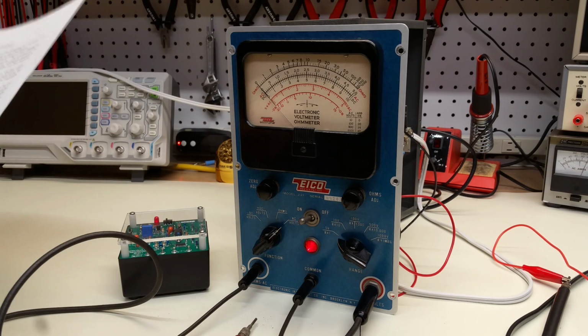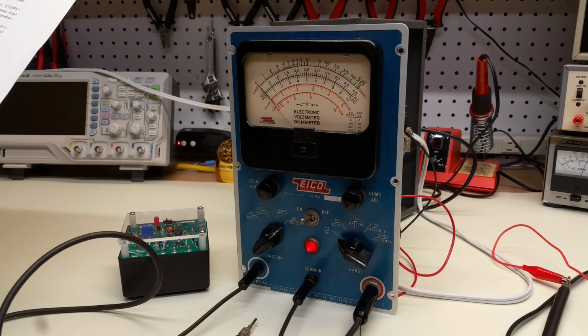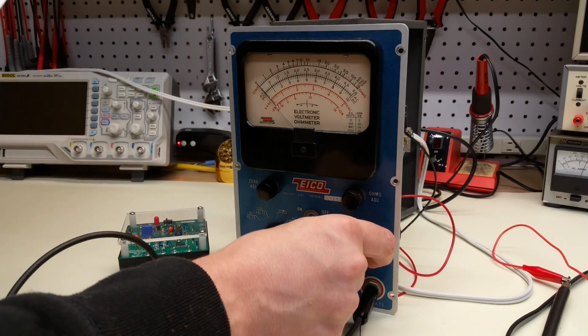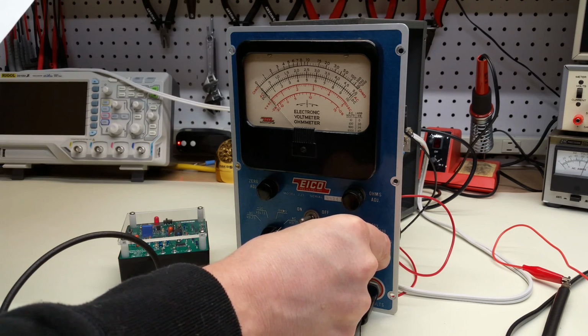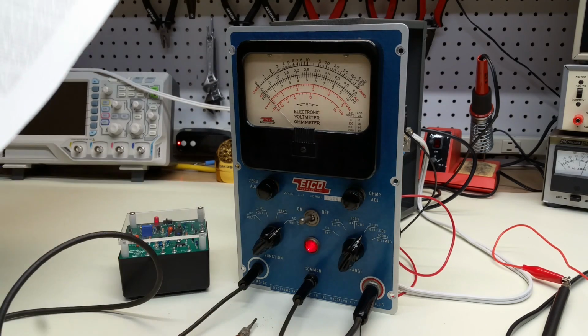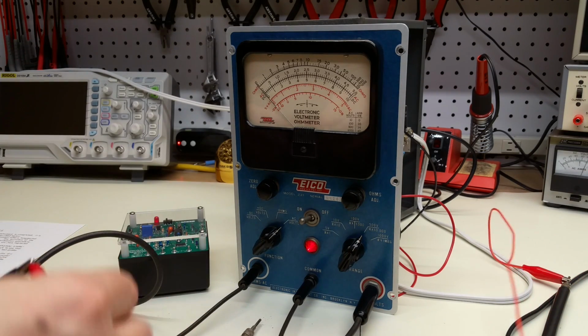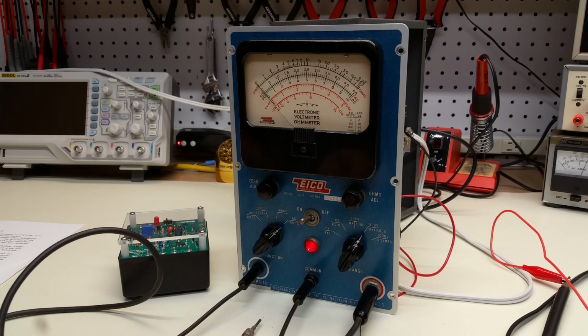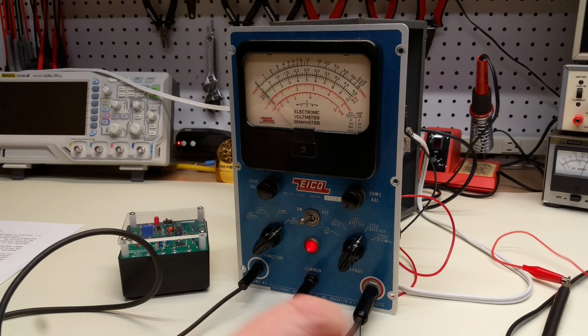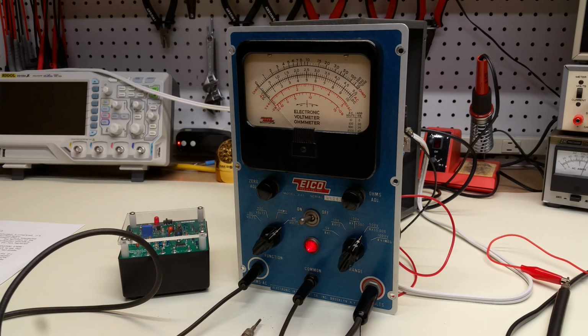And then the next step now is to connect the leads up to the AC supply on the 500 volt position. So there's 100 volts and there's 500 volts. And then to make the final calibration on the AC cal pot, which turns out to be R30 on the top of the back rack. So let me hook up the AC and do that.